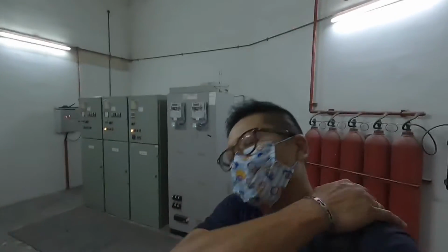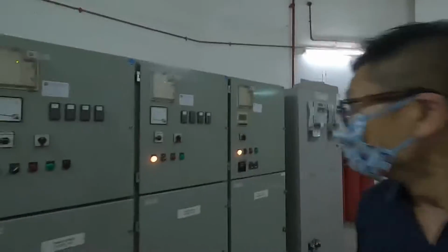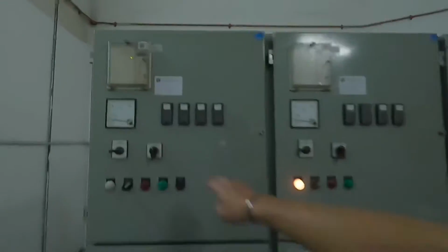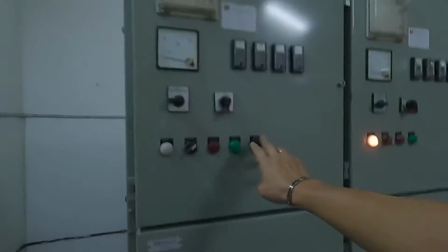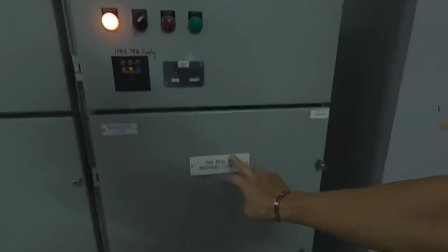Okay, this is the Ritz Carlton Hotel Residences HV room, 11 kV. Okay, today I'm inside this room just to check the normal parameters to make sure everything is in good condition. Alright, here we have the VCB panel, transformer 1, transformer 2, and this is the incomer.